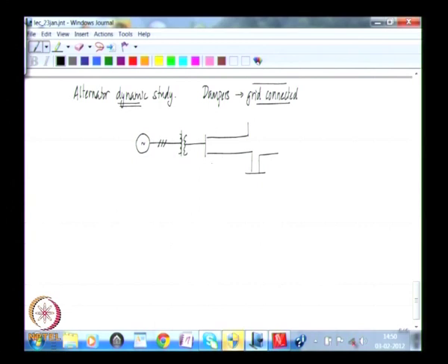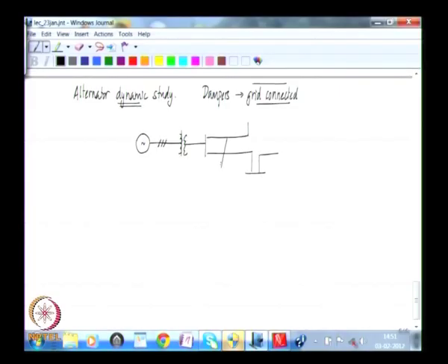Whenever you design a machine and you are going to design the switch gear to protect the machine and make it operate in a safe manner on the grid, one has to answer the question, what is the worst case situation that we are likely to encounter? And in that analysis what one does normally is to look at fault performance of the machine. So if there is going to be a ground fault on the lines, what happens to the machine?